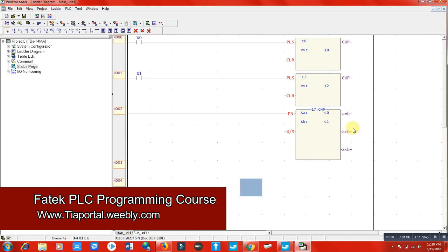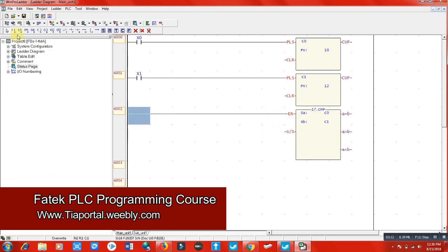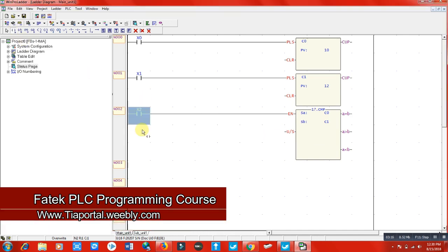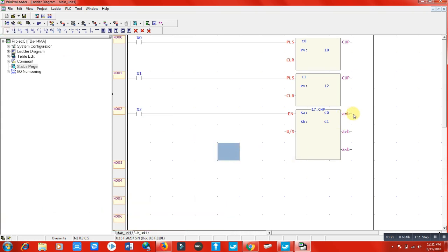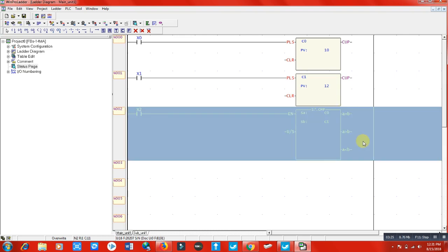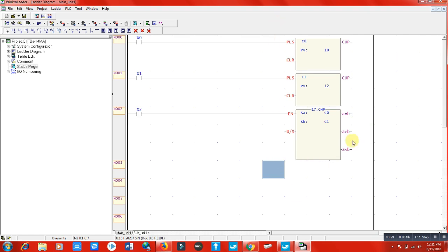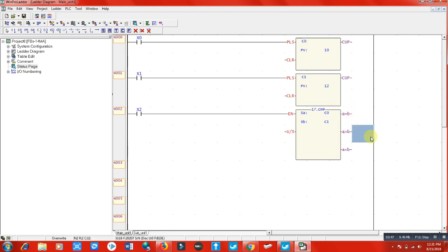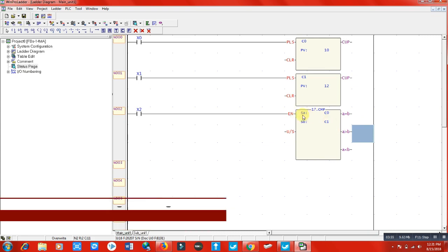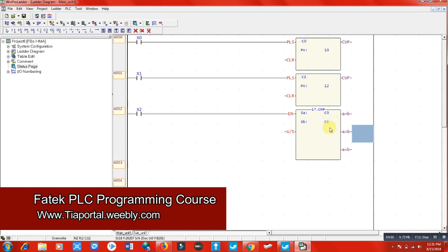After clicking OK, the comparison box appears with some functions. EN is the input, so we have input directly or we can use input terminal x2 — that's our switch for the comparator. There are three outputs, because these sections are the output sections and these are the input sections. So: when A equals B, what output do you want switched on? Here, A is c0 and B is c1.